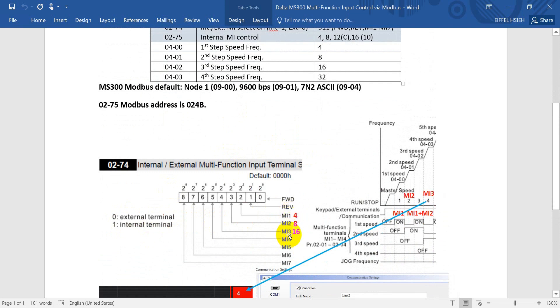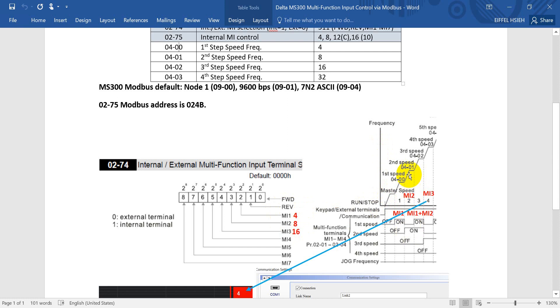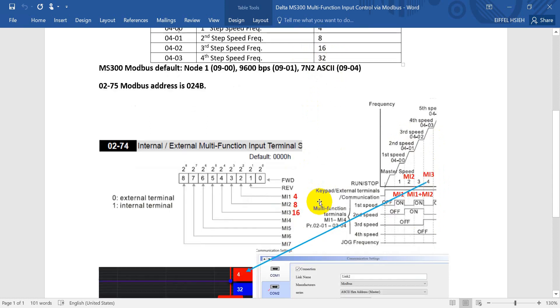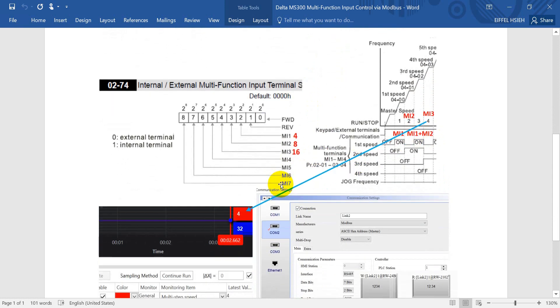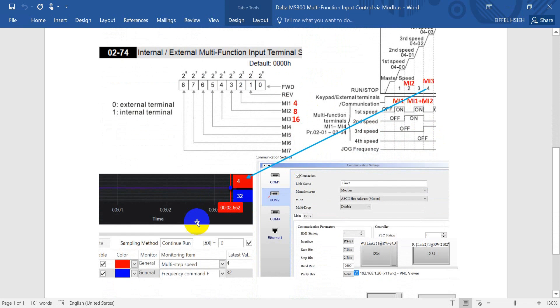Next we will simply use MI1, MI2, and MI3. Here you can see the multi-step speed: for the first step speed, means only MI1 on. Second speed is MI2 on. Third speed means MI2 and MI1 both on. Fourth speed is MI3 on. We basically just use these four values to control.